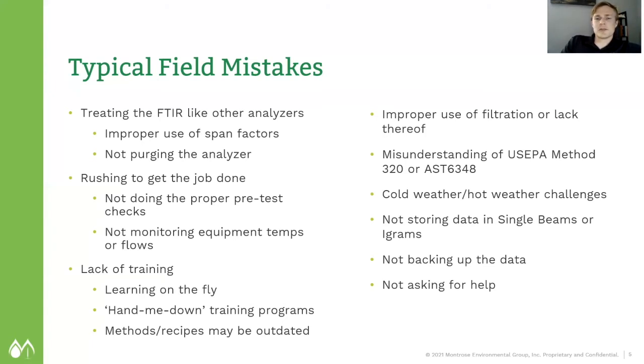improper use of filtration. We believe in filtering right at the top, right behind the probe, so your heated line is nice and filtered. There is an argument here as to whether that's needed or not, but to me, good scientific process, you're keeping your line clean. If you have filtration after the heated line, you're potentially building up a bunch of gunk in there, which could lead to off-gassing, could be impacting the sample. Once again, lots of arguments back and forth, but we find best practice is to filter at the top of the system.